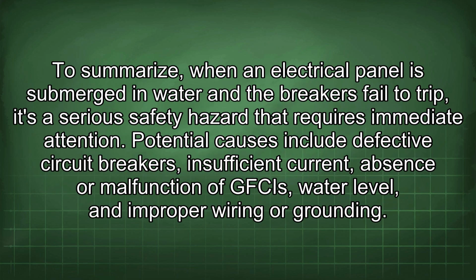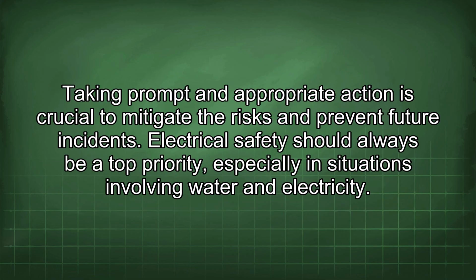To summarize, when an electrical panel is submerged in water and the breakers fail to trip, it's a serious safety hazard that requires immediate attention. Potential causes include defective circuit breakers, insufficient current, absence or malfunction of GFCIs, water level, and improper wiring or grounding. Taking prompt and appropriate action is crucial to mitigate the risks and prevent future incidents. Electrical safety should always be a top priority, especially in situations involving water and electricity.